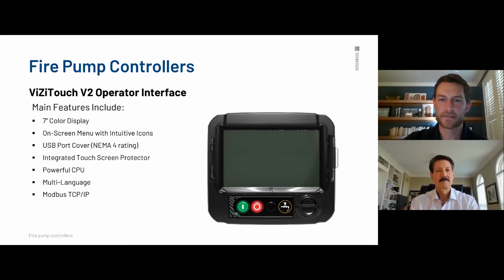But it's got this USB port right here. I did show you that picture earlier. The ViZiTouch is actually rated for NEMA 4, including this USB on here as well. The whole controller again is NEMA 2, but the ViZiTouch as a standard is rated NEMA 4. And it's actually got multi languages. We have Modbus. Marty mentioned that earlier. Modbus TCP/IP is standard on the ViZiTouch.